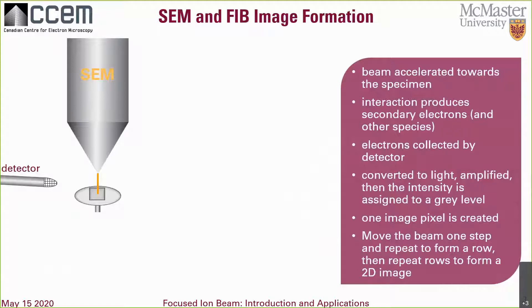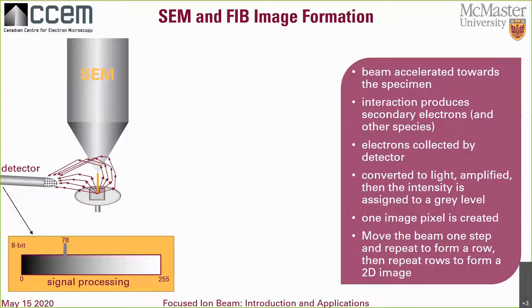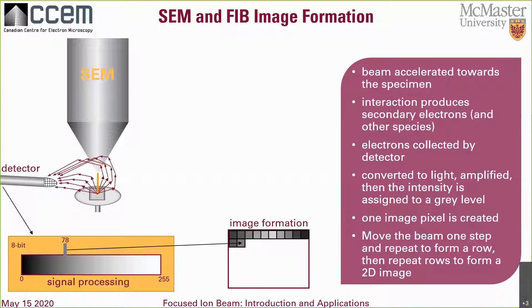In case you missed our webinar last week about SEM by Chris Butcher, here's a very quick explanation about image formation. An SEM uses a beam of electrons accelerated towards a sample and focused with magnetic lenses down to a small spot for a set dwell time. This interaction produces secondary electrons collected by a detector, assigned to a gray level from black to white to form one pixel of an image. The beam is then moved over one increment and the process repeats to form a 2D grayscale image.